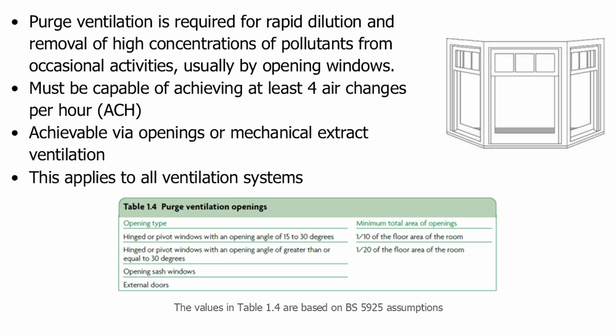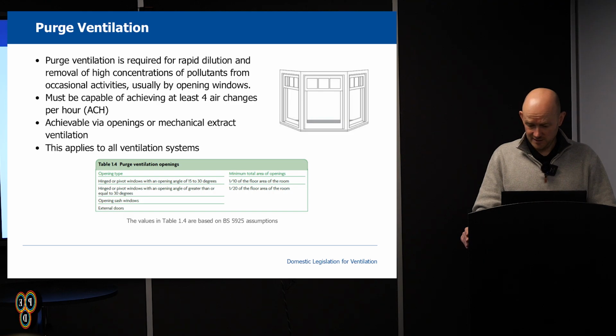Where purge ventilation is delivered through openings such as windows in a habitable room, the minimum opening areas, which are specified in table 1.4, should be achieved. There are minimal changes when compared to the 2010 edition, where previously it distinguished between doors and windows. These have now merged into the table known as 1.4. Purge ventilation applies to all ventilation system types within Approved Document F.